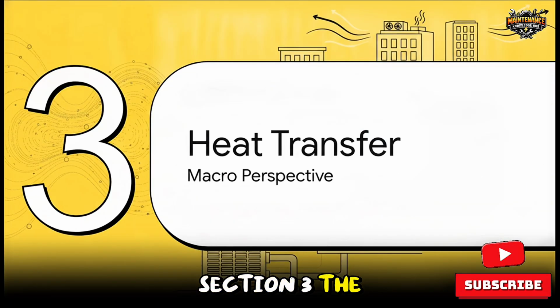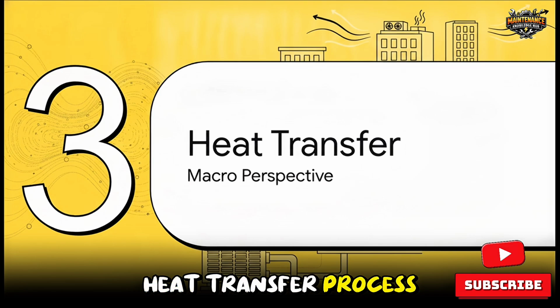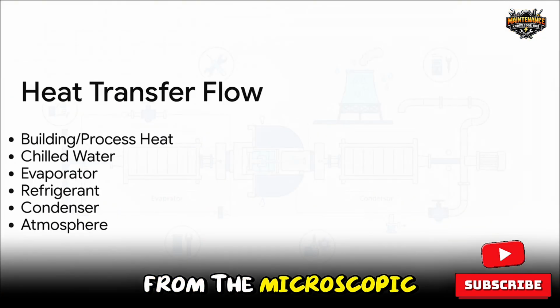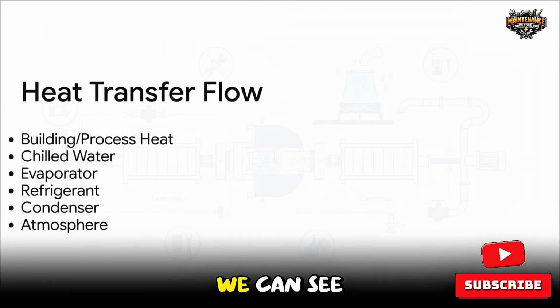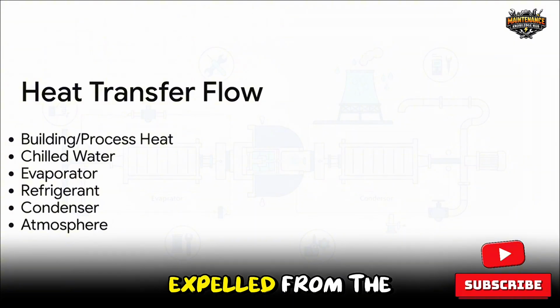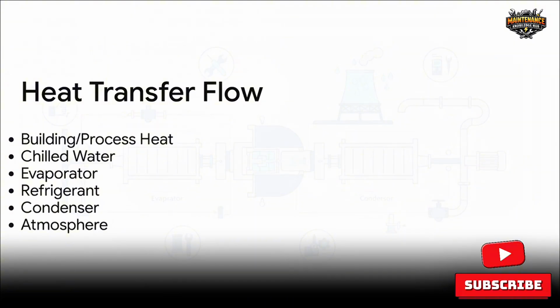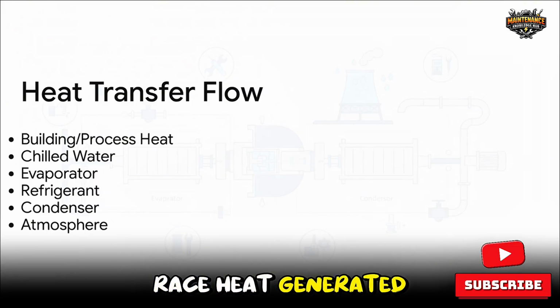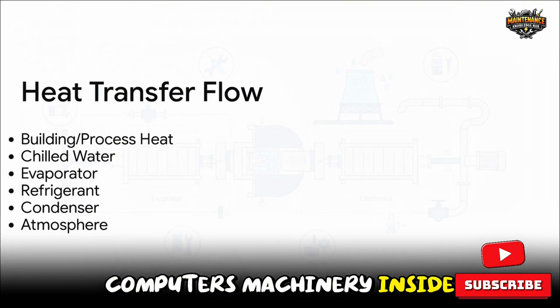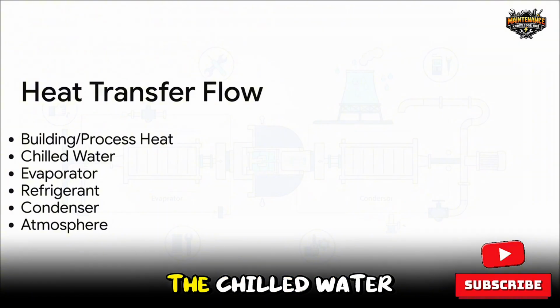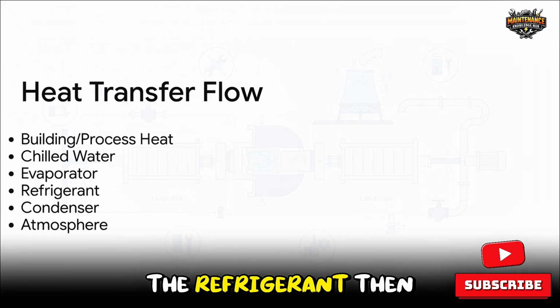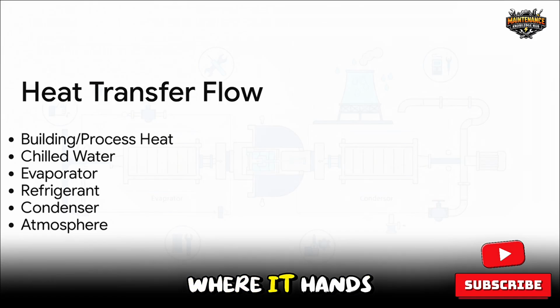Section 3. The heat transfer process. So if we zoom out from the microscopic level of the refrigerant, we can see how heat is systematically expelled from the entire building. It's essentially handed off like a baton in a relay race. Heat generated by people, computers, machinery inside the building, all of that is transferred to the chilled water. The chilled water carries it to the evaporator, where it passes the heat baton to the refrigerant. The refrigerant then carries it over to the condenser, where it hands it off to a separate cooling water or air system.